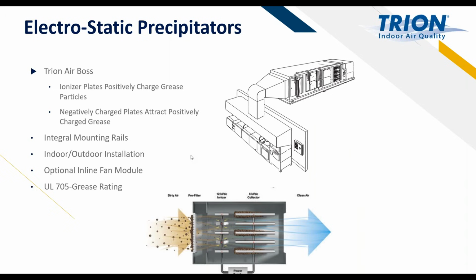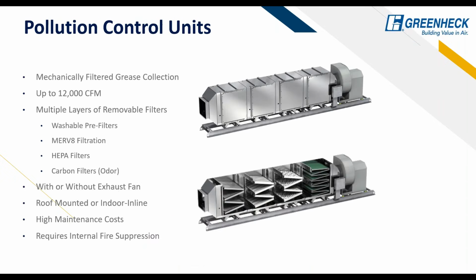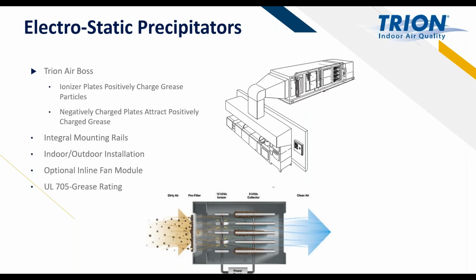Going into Trion, we also represent a company called Trion, and they make electrostatic precipitators. So basically, just some charged plates within this unit here, going across a pre-filter into the charged plates, and it'll just collect that, and then it'll automatically wash every night. So just another option to help grab that grease and collect it somewhere. And this will also have its fire system in there. Both these PCUs, this one and these ones, can be mounted indoors or outdoors, but they are quite large. I just want to reiterate that. They do get quite big quite quick.